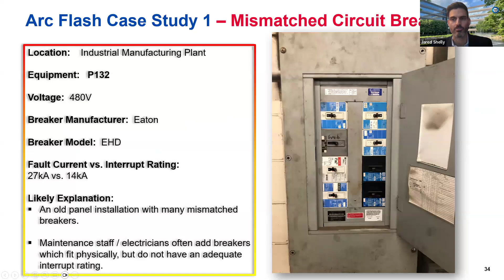Sure. Case study number one is a classic situation where you have an older power panel, and you may have a need for adding a breaker to it. The breaker might be added by a qualified electrician and might physically fit, but it doesn't have the appropriate electrical engineering adequate interrupting rating—it gets thrown in there over time, not as originally designed or intended. The fault current isn't properly sized, and this could lead to it not performing as designed, potentially causing it not to clear, resulting in a fault incident that might go further upstream or downstream at a higher level, leading to a more catastrophic incident.